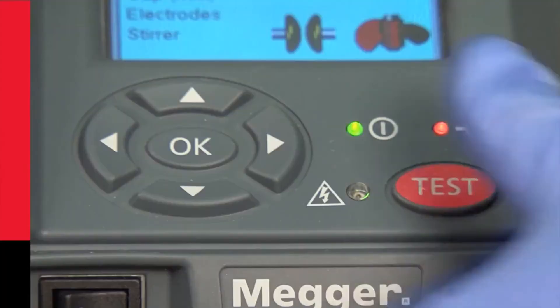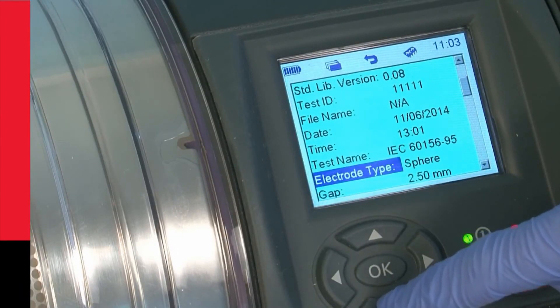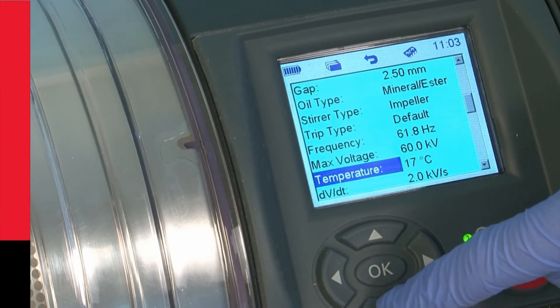Remember, a sample should only be tested once, and IEC require that the oil sample be tested at a temperature between 15 and 25 degrees centigrade, and ASTM 20 and 30 degrees centigrade. And the temperature needs to be recorded with the test results, of course.